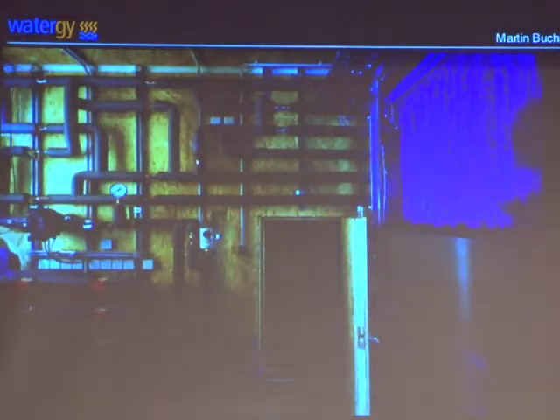And we also built a second prototype in Berlin, which is about a facade greenhouse. And this greenhouse is functioning the same way. We have the same circular air circuit with a cooling tower, which then is in the building. But the emphasis here is to produce heat for using this greenhouse as a kind of solar collector. This is quite complicated. We produce humid air in the greenhouse, and by a process with using desiccants, we can transfer humidity into heat, and by this can have at cooler temperatures in the storage can produce hotter air in the building. There are some pictures of this greenhouse. This is a technical room with the heat exchanger, which is the same one than in the Almeria prototype.